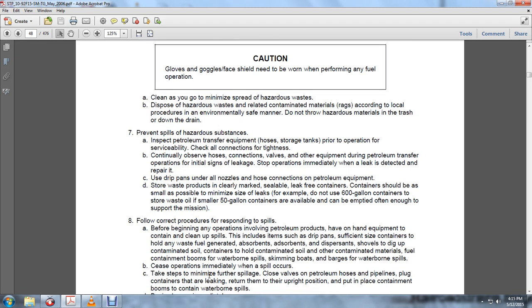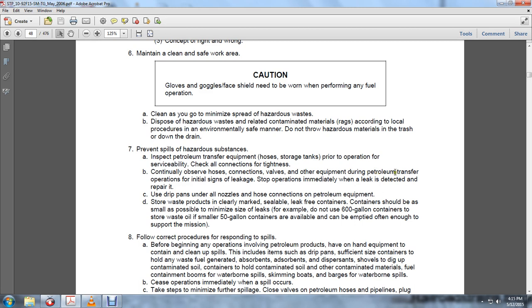Inspect petroleum transfer equipment, hoses, and storage tanks prior to the operations to ensure they are serviceable. Check all connections for tightness. Continually observe connections, valves, and other equipment during the petroleum transfer operations for initial leakage. Stop operation immediately if there is a leak, and detect and repair it. Use drip pans under all nozzle and hose connections of the petroleum equipment.